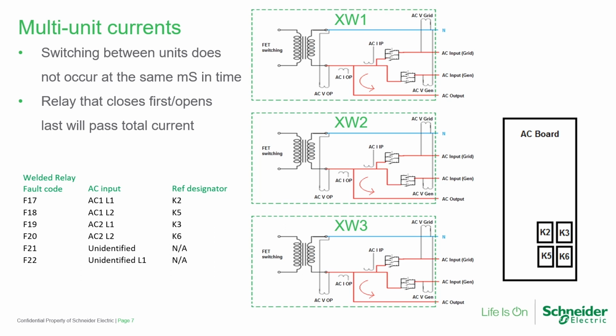On the screen here, you can see 3 inverters represented, each with their inputs and outputs labeled. And so the internal relays are also represented. On the left, you see the different welded relay fault codes, and it tells you exactly which relay is welded. On the right, it will identify the locations of those relays on the AC board itself.